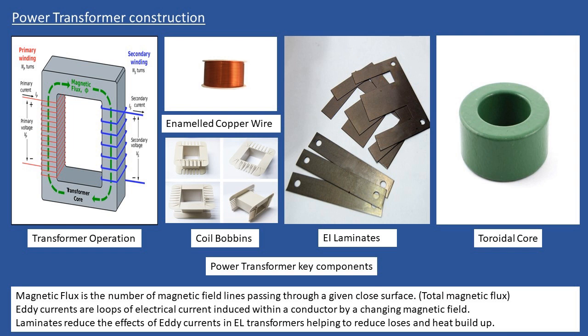But you might question, well, why would you make a transformer using these metal plates? Well, the reason for that is something which we call eddy currents, and what you don't want in any kind of transformer is excess generation, or induced eddy currents. And the problem with eddy currents is twofold. When you look at transformer designs, they are extremely efficient when you look at either stepping up or stepping down voltage. It could be in terms of efficiency of maybe 98 or even 99%. But if the transformer design is not very good, what will happen is that you have these eddy currents which are created, and that reduces the overall efficiency of the transformer.